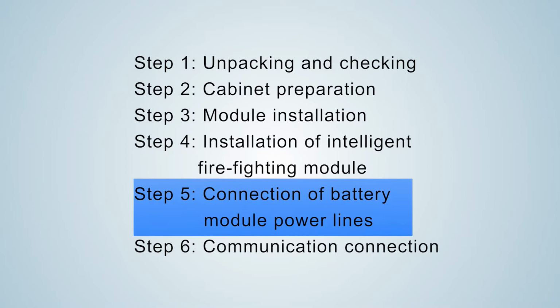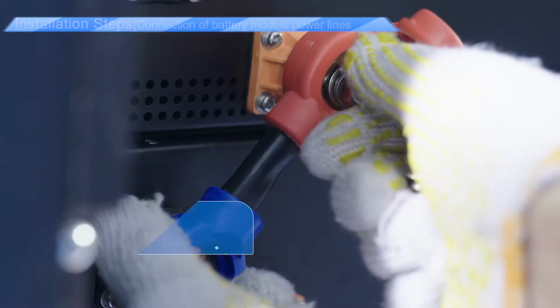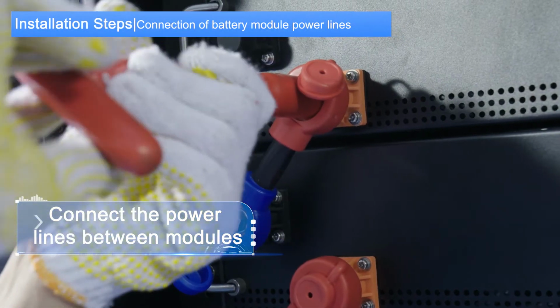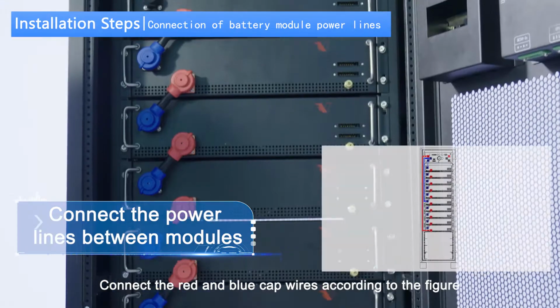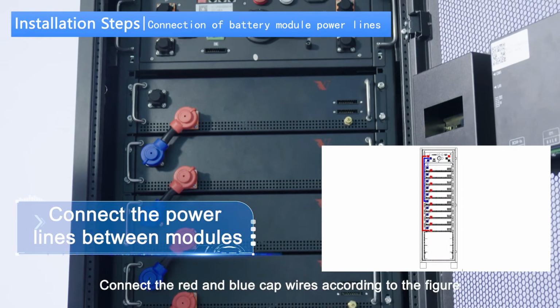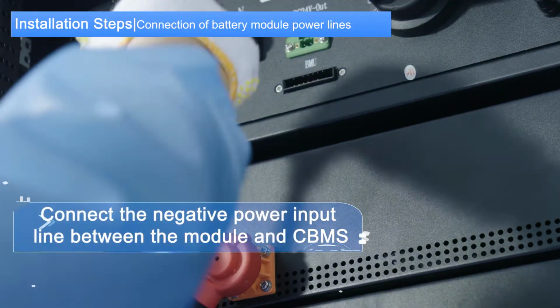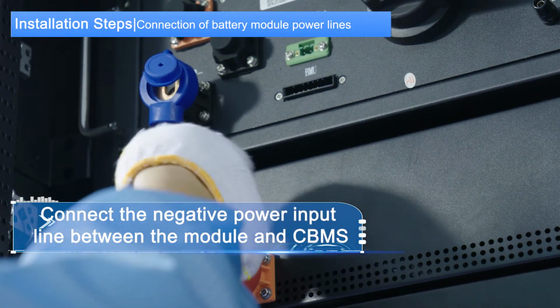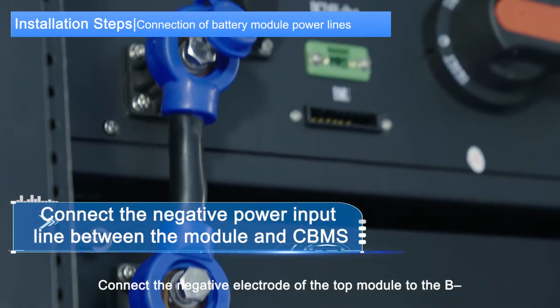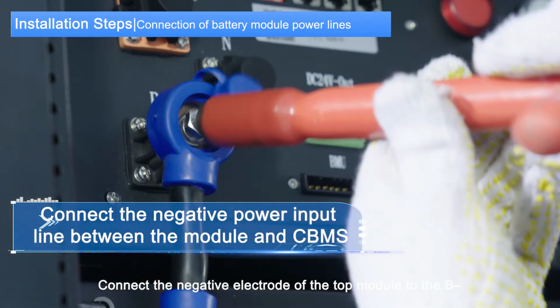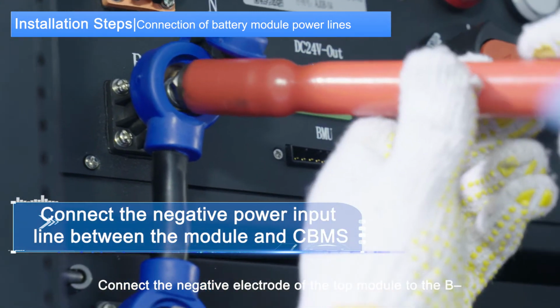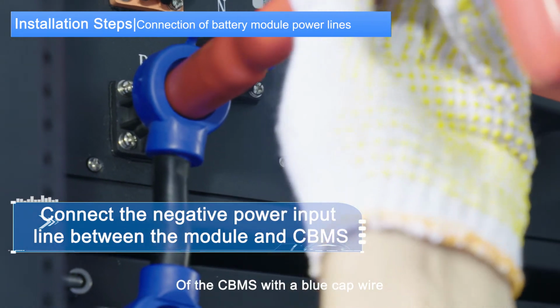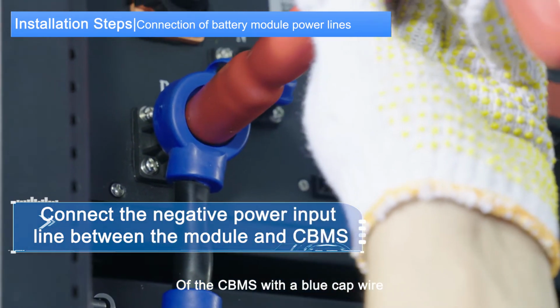Step 5. Connection of battery module power lines. 1. Connect the power lines between modules. Connect the red and the blue cap wires according to the figure. 2. Connect the negative power input line between the module and CBMS. Connect the negative electrode of the top module to the B negative of the CBMS with a blue cap wire.